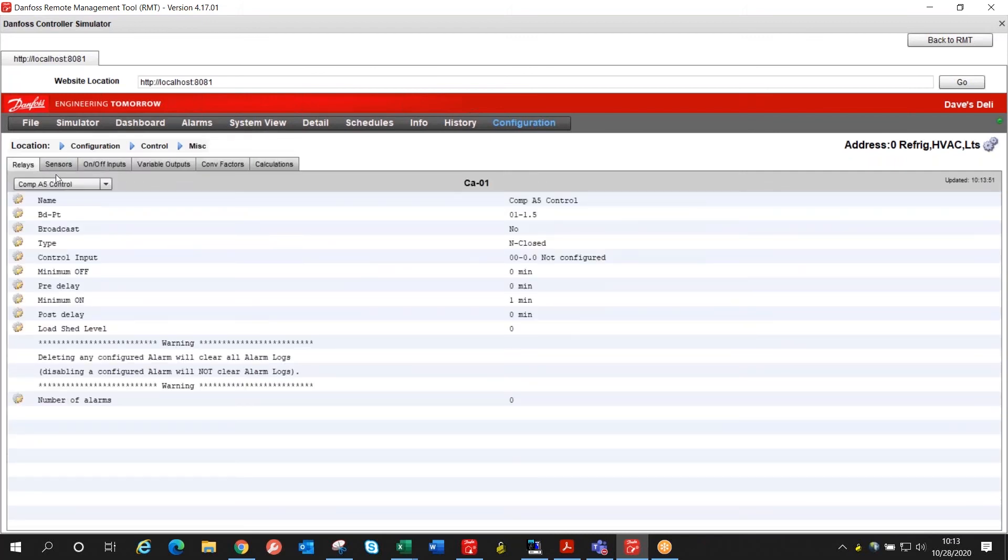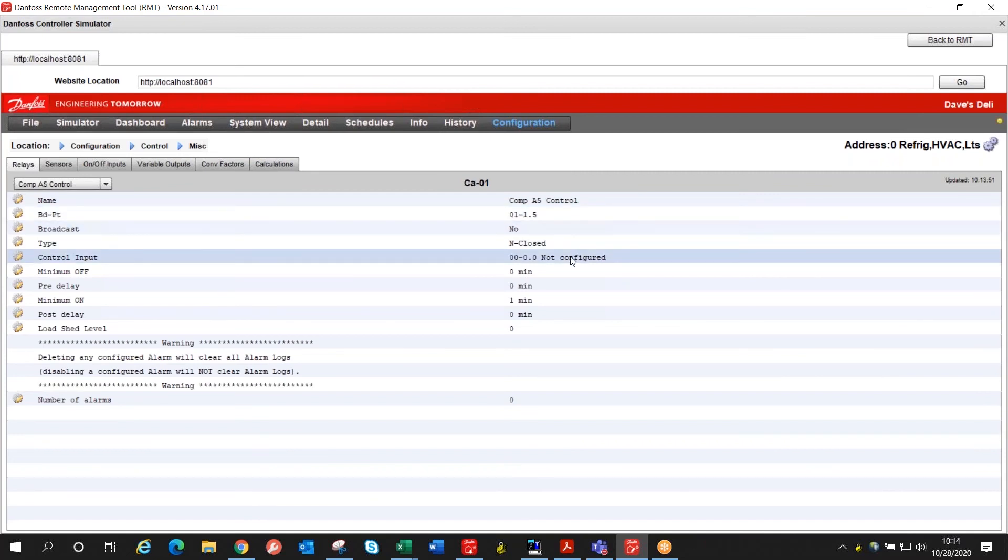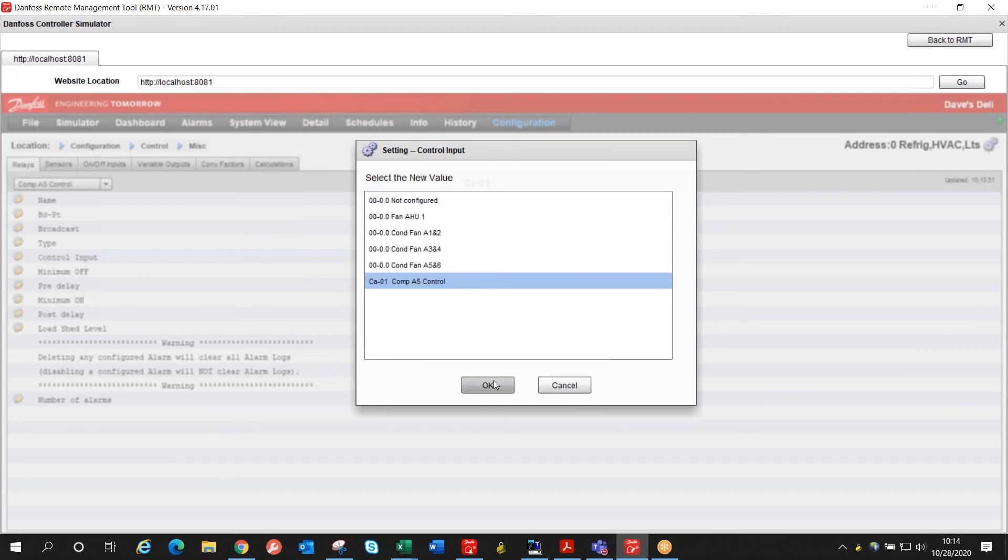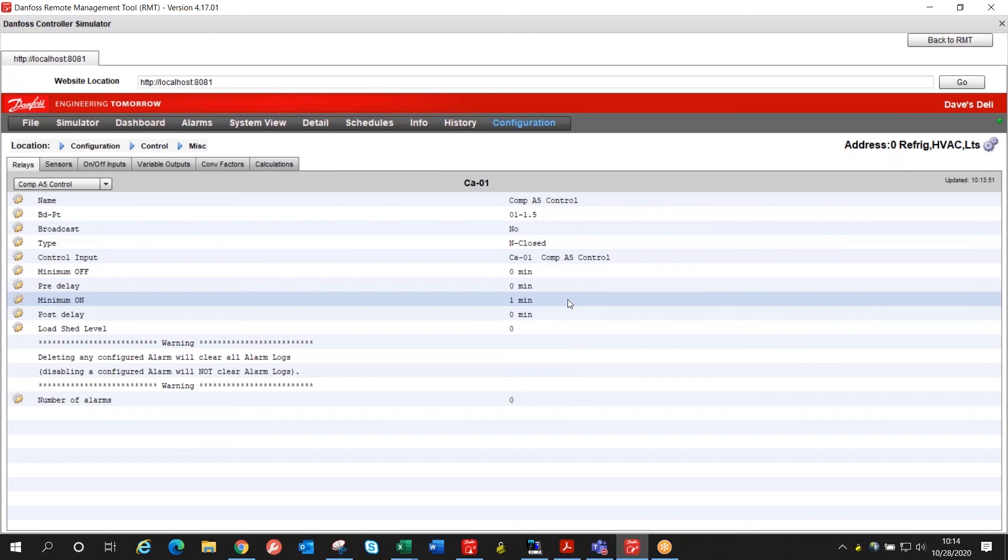Switch over to relays. I've set up the name for this miscellaneous relay. The actual board point for the compressor and now I need to link the calculation we just built with this miscellaneous relay output. Here's our calculation number one. We program that in and I also set a minimum on time just to be sure that it doesn't short cycle for any reason but with the schedule that should be a non-problem for us.